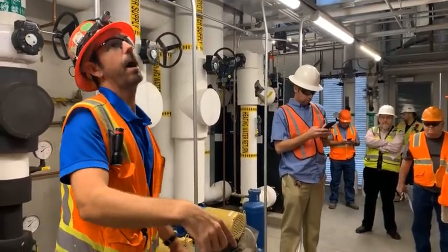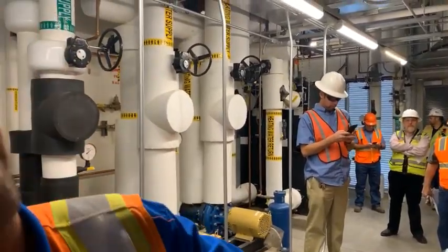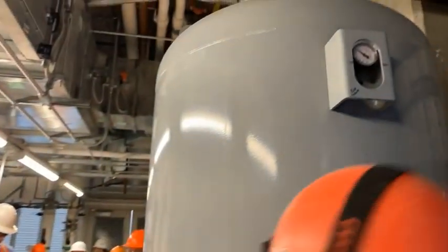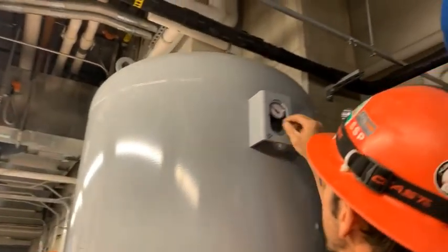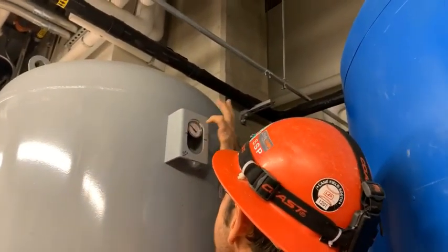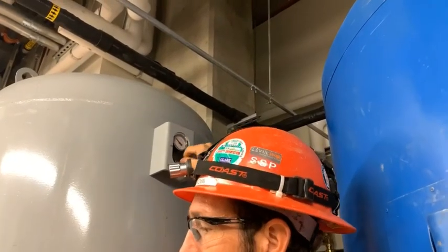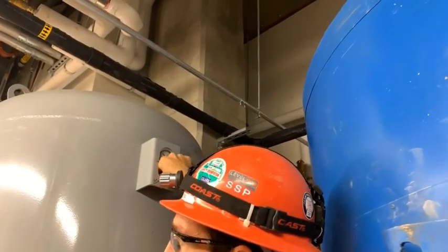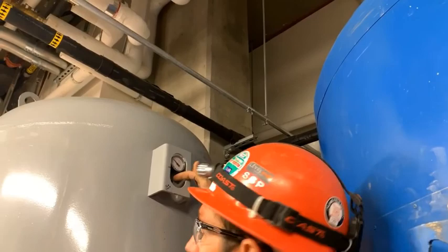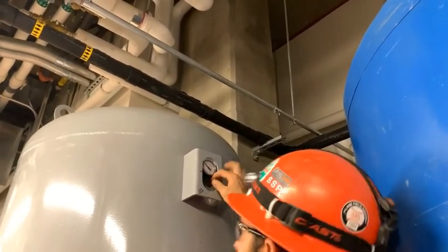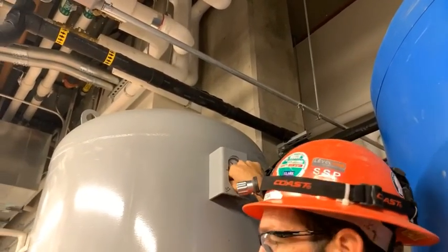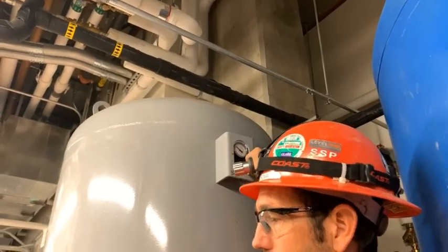Once the pressure is off, I think this guy is right here. There's an air Schrader port right here. There's a gauge on the side of the tank. I like to use my own gauge. This one was a little harder to get to. I had made like a little Schrader extension that you can swivel on here. You'll take this cap off, put your gauge on, read the pressure.